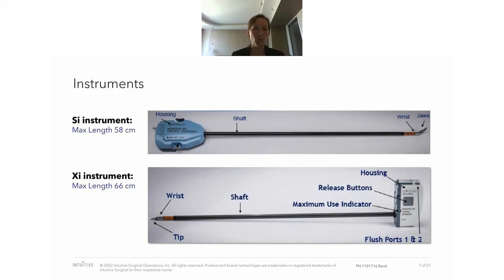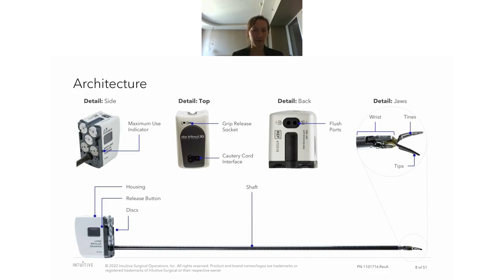Now, going a bit more into what is actually in the housing, you can see a maximum use indicator, which does not exist on the SI instrumentation. That indicator shows when the instrument has reached its maximum uses, when it turns red. If you see a dot on the instrument, that means it has exceeded its uses and cannot be put on the robot again. Then there's the grip release socket. For the cautery instruments, there is the cautery cord interface where you can attach the cords. And then, very important for reprocessing.